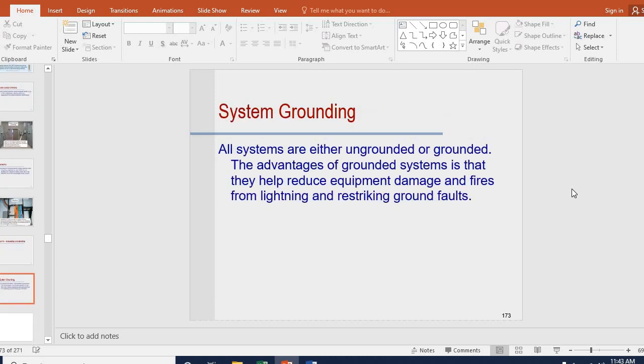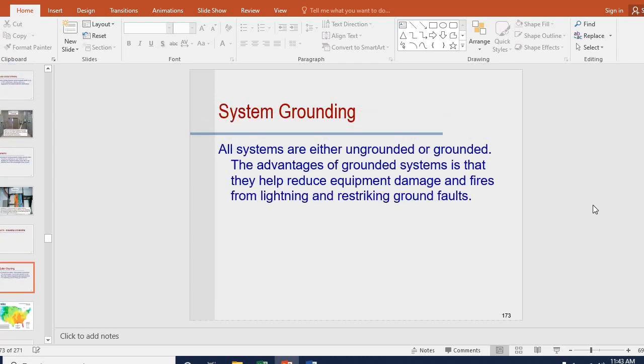Grounding and bonding. All systems are either ungrounded or grounded. The advantages of grounded systems is that they help reduce equipment damage and fires from lightning and restriking ground faults. Very important.